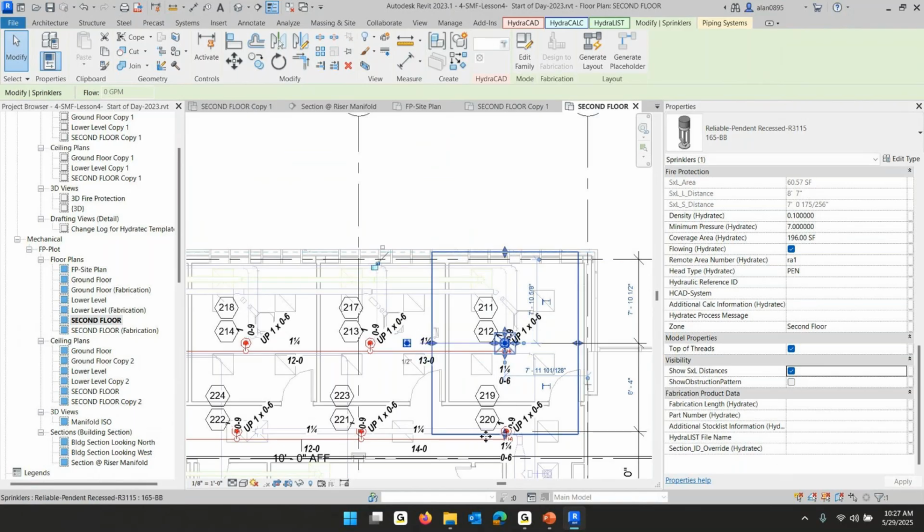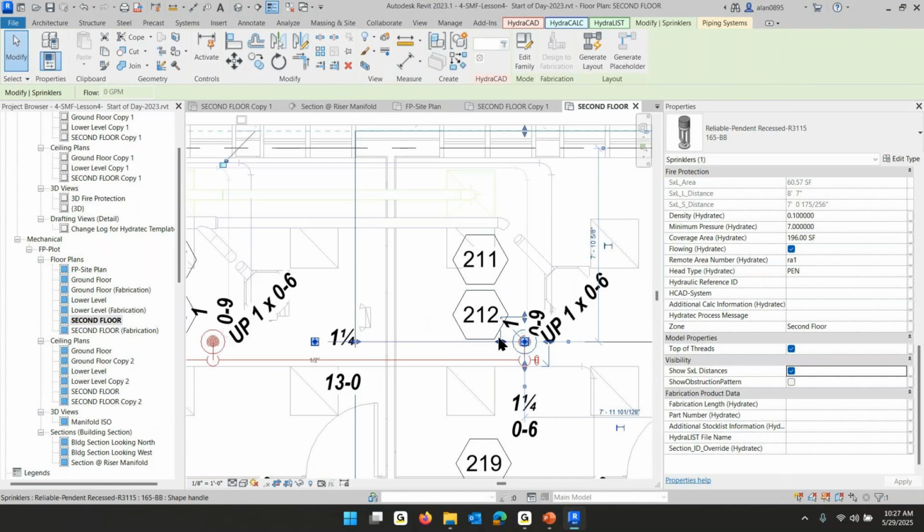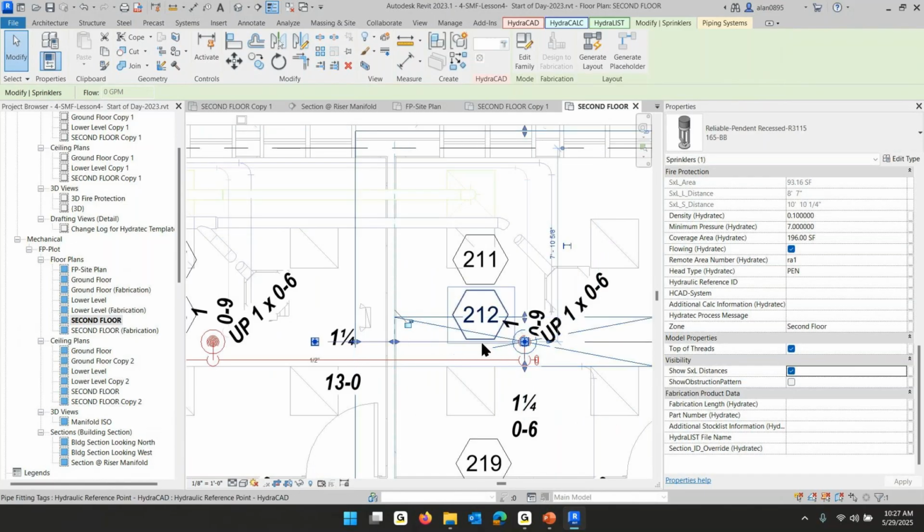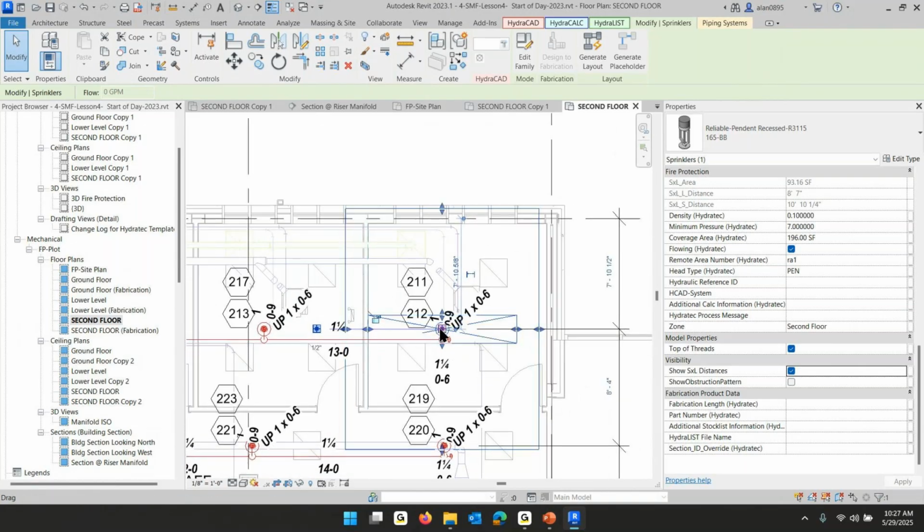But because we're in a room, that doesn't really count at all. It's this one. If I take the inner box and I bring it up to this wall, and I go the same dimension in the other direction, it doesn't make it to that wall, does it, Tom? Nope. So the furthest wall would be over here. If this sprinkler is covering to that wall, then it's covering beyond the other wall.